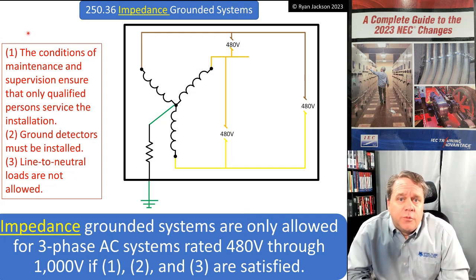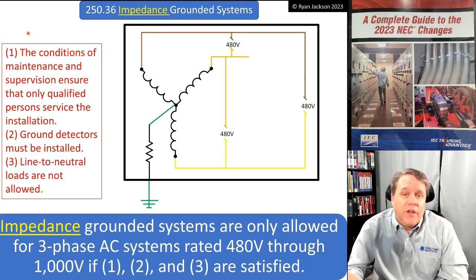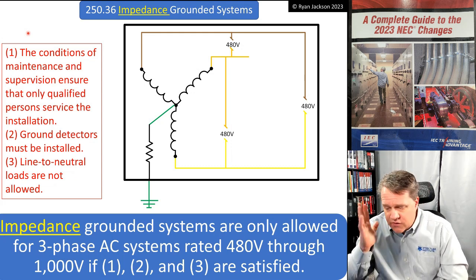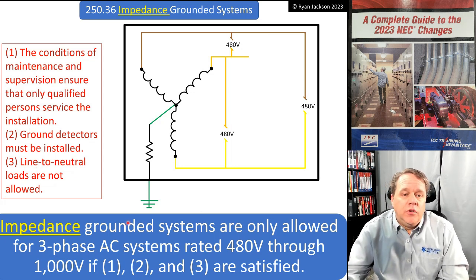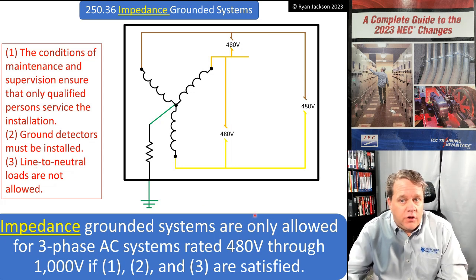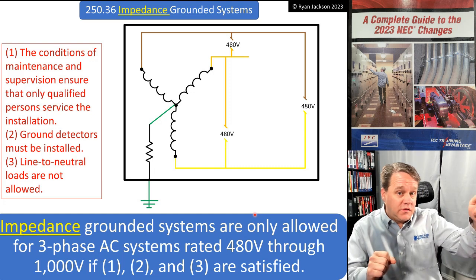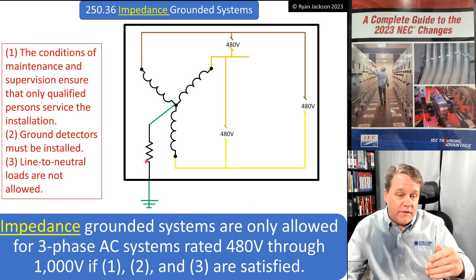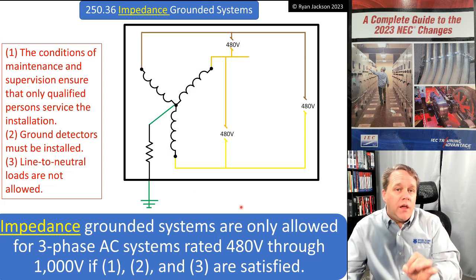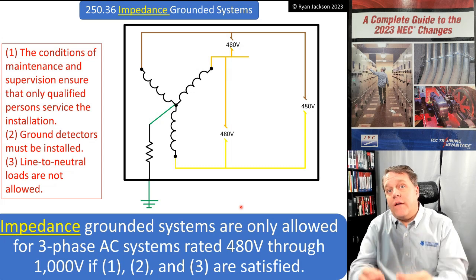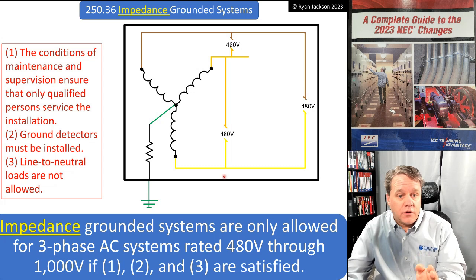Condition one: conditions of maintenance and supervision must ensure that only qualified persons are going to service the installation. You can't put this in a regular office building or a 7-Eleven - this is sophisticated stuff limited to industrial facilities. Condition two: you need to have ground detectors installed. With high impedance grounding, you set the resistance to a high value, which means you're going to have low amounts of fault current. That impedance limits the current that flows under fault conditions.